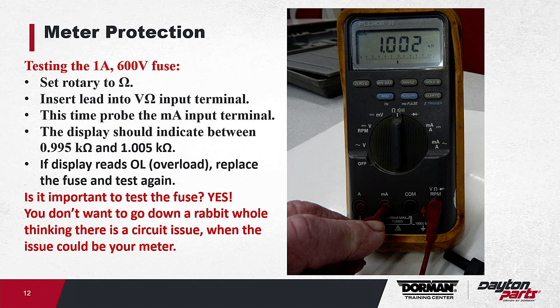Is it important to test a fuse? Yes, it is, because you don't want to get into a situation someday where you're going to take some amp readings, and all of a sudden you get an OL in there, and now you're thinking you found a problem with the circuit. It'll lead you down a rabbit hole. When all this time, it was your meter, not the circuit.